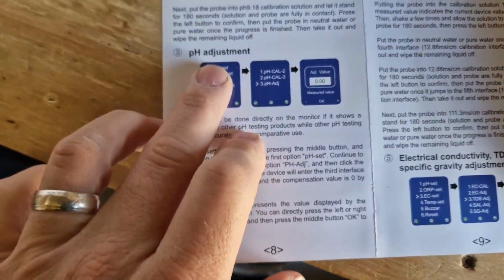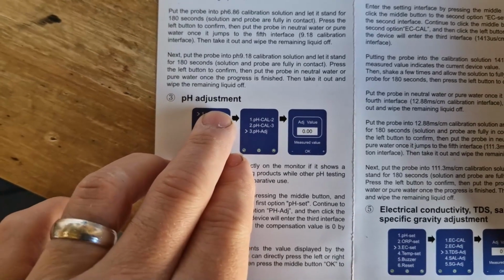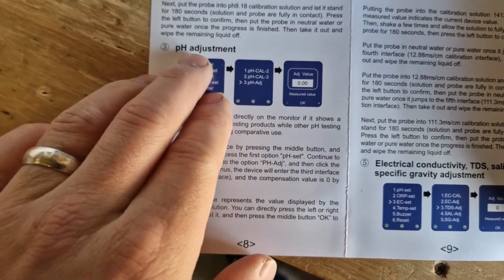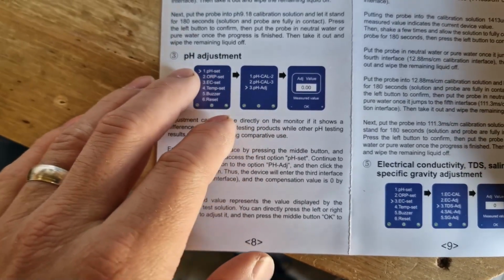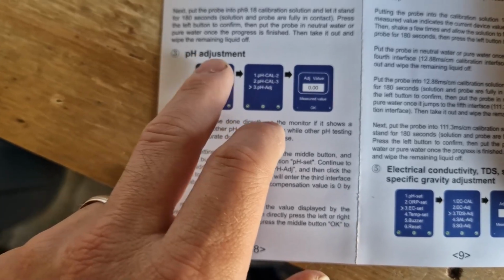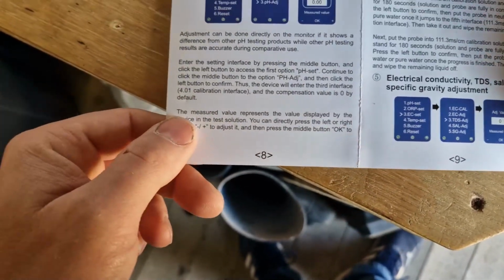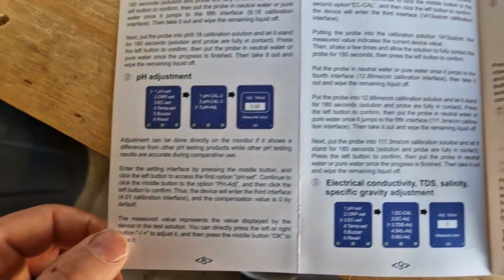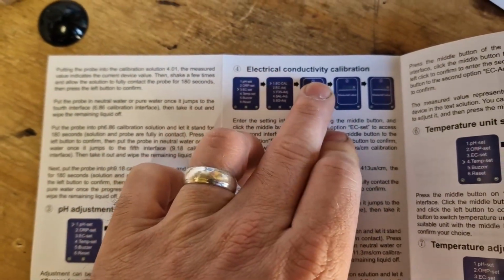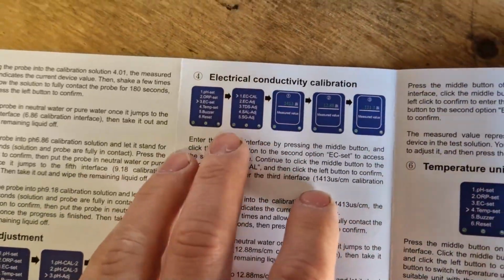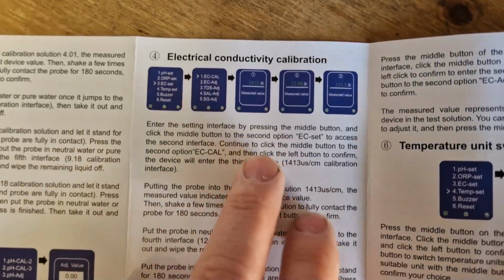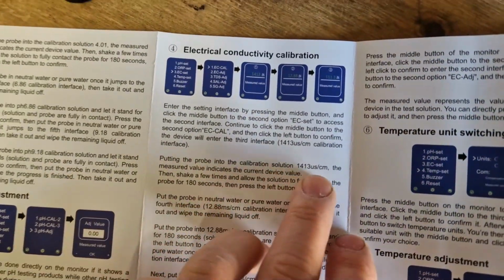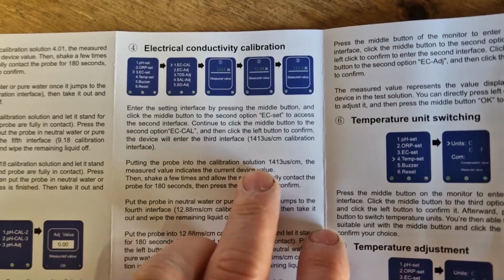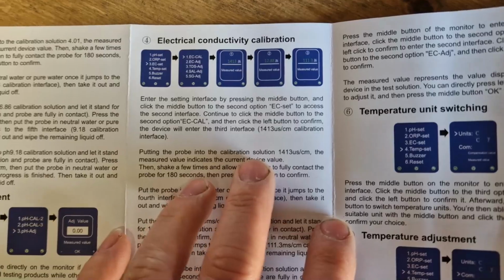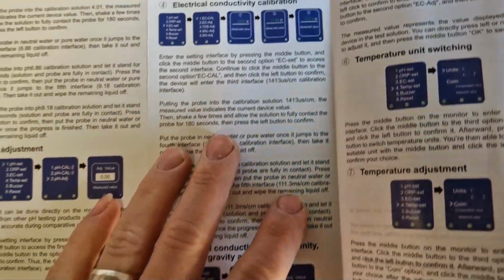Let's have a look what else. Tells you how to adjust your pH if you feel as though the pH reading isn't correct when you compare it to other pH readers. So that's that. Electrical conductivity calibration, so you can calibrate that within the monitor itself. Obviously you have to use electrical conductivity calibration solution to do that, which they don't send with it, so you would have to get some of that yourself.